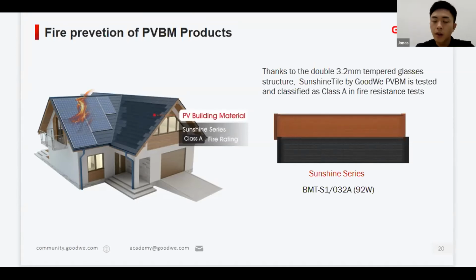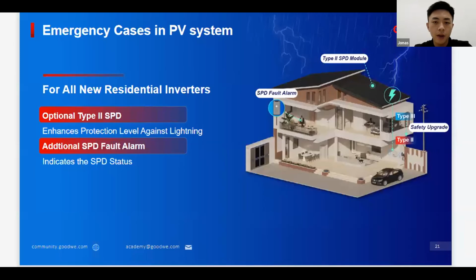So, okay, and this is the solution regarding fire. Sometimes in some regions, storm lightning is also very normal. The installations of PV plants, because of their exposed nature and large collection areas, make them vulnerable to overvoltage surges from lightning. In a lightning-prone area, lightning-induced failures can be more detrimental to solar equipment. SPDs are particularly critical to protect against damage from surges, including direct lightning strokes and indirect lightning.